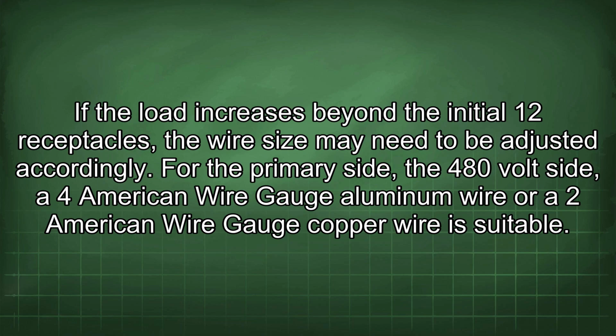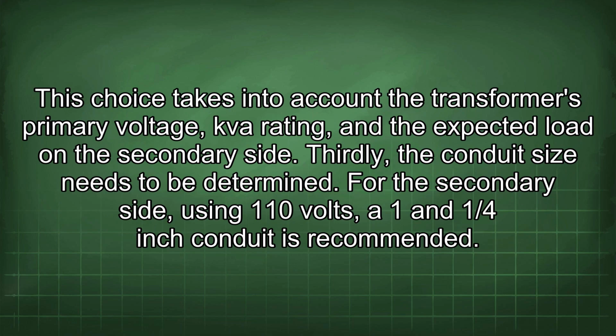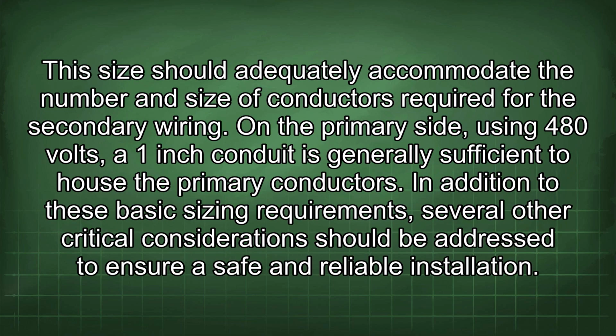If the load increases beyond the initial 12 receptacles, the wire size may need to be adjusted accordingly. For the primary side, the 480 volt side, a 4 American wire gauge aluminum wire or a 2 American wire gauge copper wire is suitable. This choice takes into account the transformer's primary voltage, kVA rating, and the expected load on the secondary side. Thirdly, the conduit size needs to be determined. For the secondary side, using 110 volts, a 1 and 1/4 inch conduit is recommended. This size should adequately accommodate the number and size of conductors required for the secondary wiring. On the primary side, using 480 volts, a 1 inch conduit is generally sufficient to house the primary conductors.